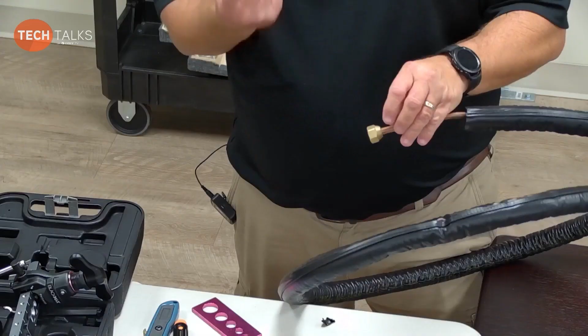And we know for a fact that if you do the flares properly and use a torque wrench to torque to specification - and I've said this in training for years - a little bit of oil goes a long way, and it doesn't necessarily have to be refrigerant oil. You need a non-detergent oil, like a Zoom oiler. One little bitty drop of oil, smear it on that surface, then a little drop on the threads. That's it, that's all you need.